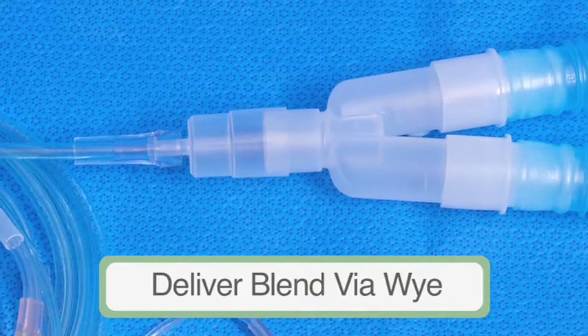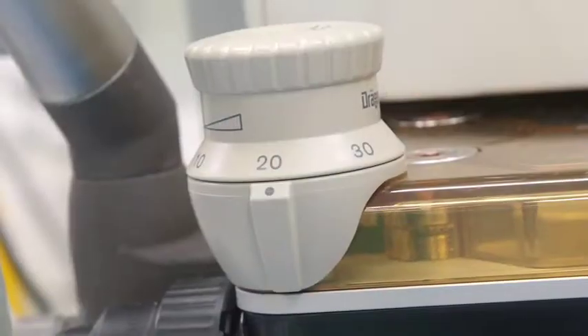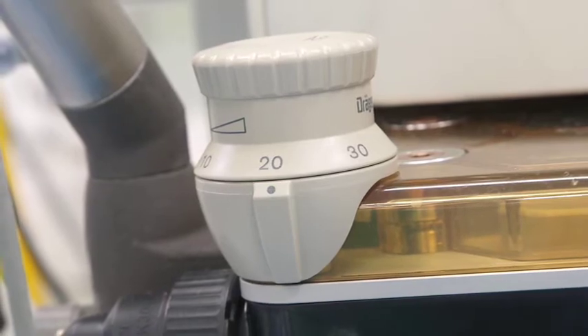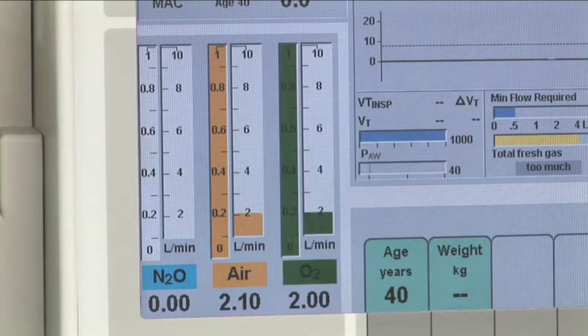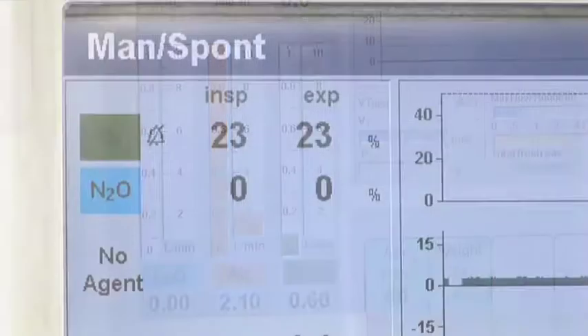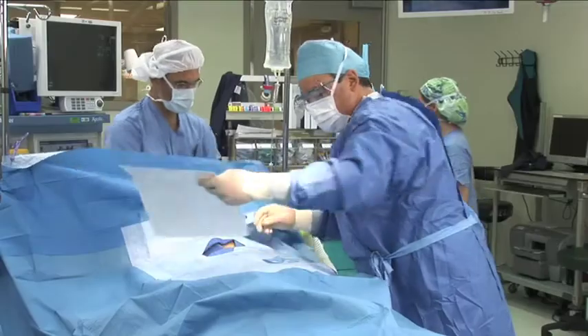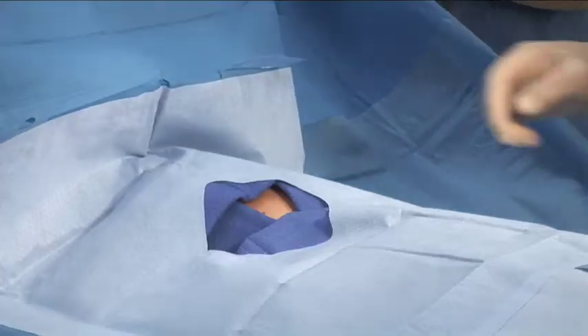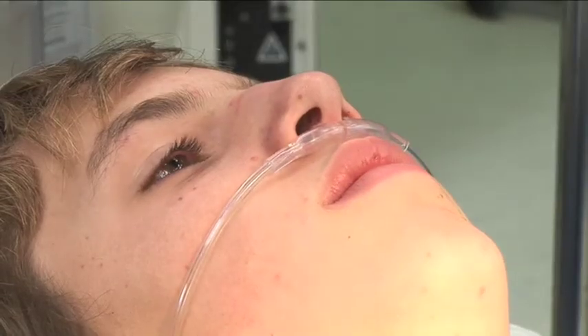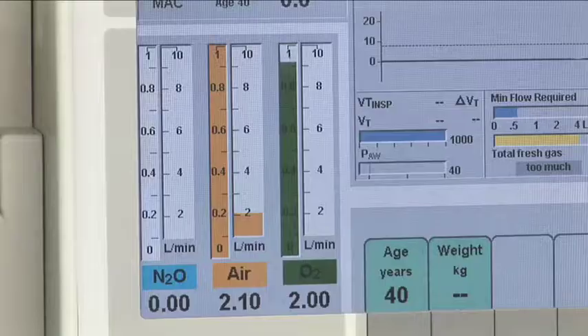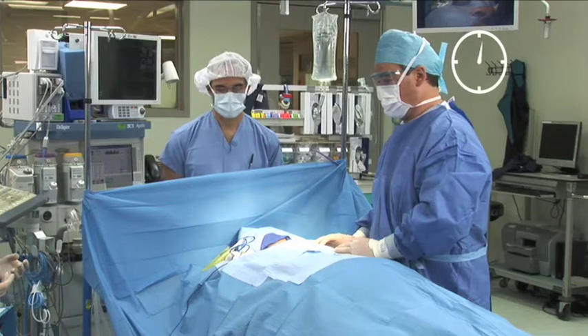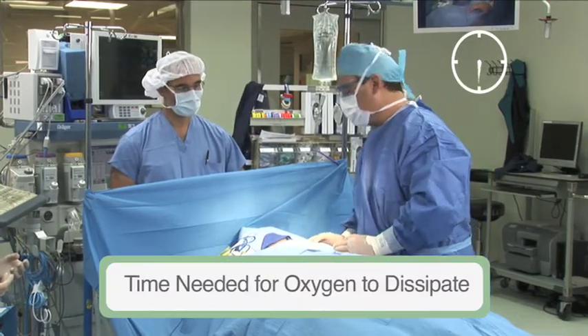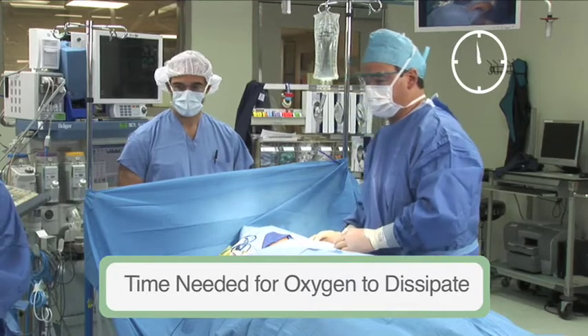For 3-gas anesthesia machines without an available common gas outlet, delivery of blended air and oxygen via the patient Y is possible. For faster changes in oxygen concentration delivery, close the APL valve. This technique has the advantage of being able to measure the concentration of oxygen delivered by the flow meters using the oxygen concentration monitor. Regardless of which open delivery method is used, if you first deliver 100% oxygen with the intent of later lowering the concentration prior to using an ignition source, it may require several minutes to reduce the oxygen concentration delivered to the patient and accumulating under the drapes.